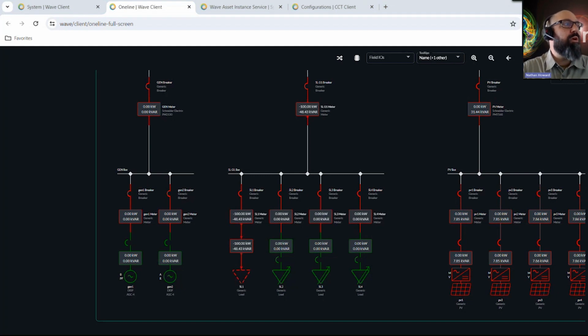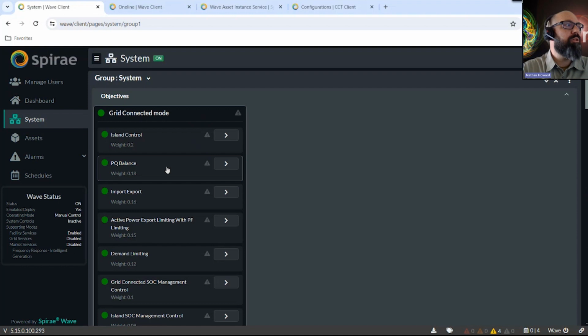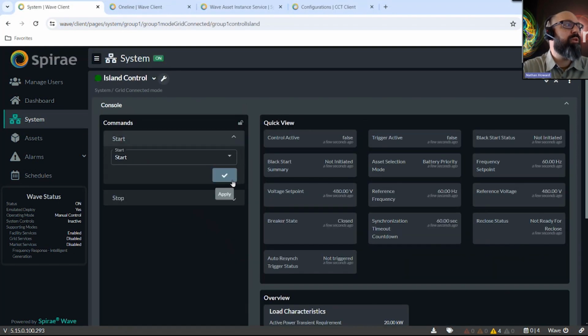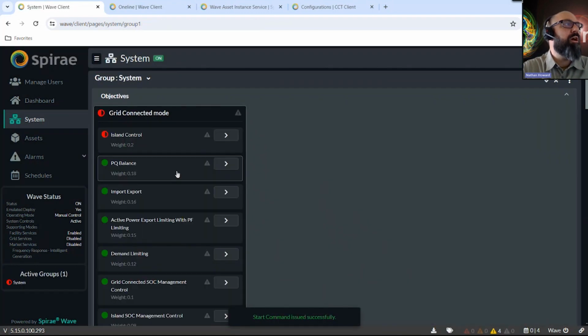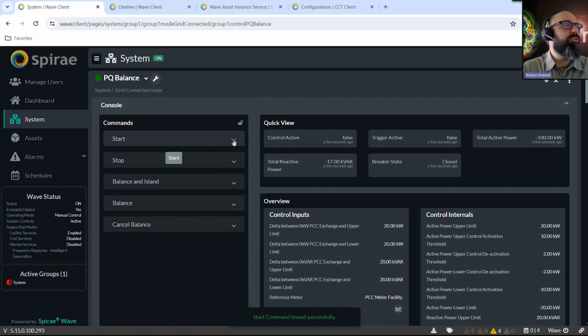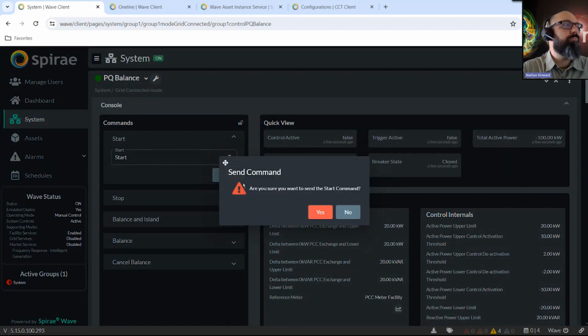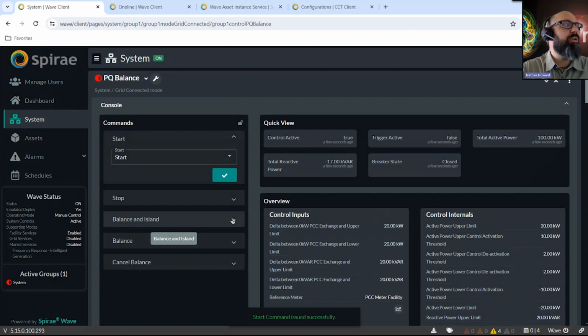So again, that primary load is online, being fed by the grid. And so now we're going to go to our system control, and we're going to use what's called the PQ balance control. So in preparation for island, we're going to make sure the island control is running and ready for us to make that transition. What that'll do, it will basically bring on those conventional generation resources. So when we do make the transition, we have a frequency and voltage master that'll maintain a stable island for us.